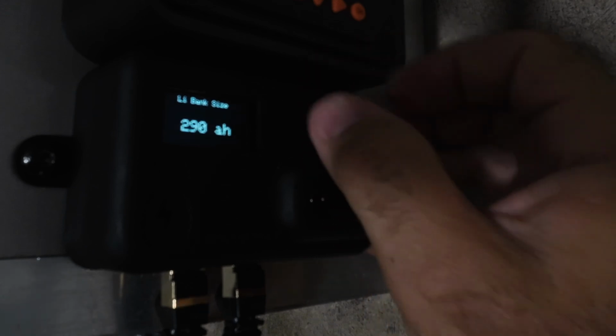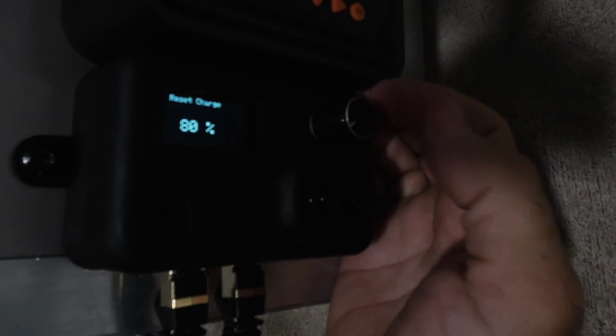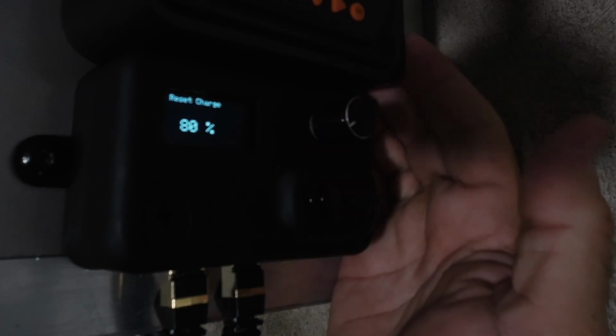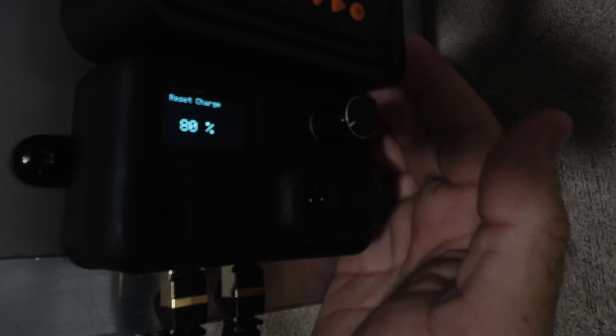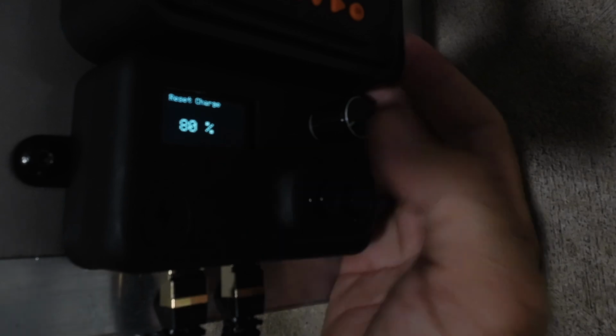And the thing that everybody has to set is how big is your lithium bank, and we're going to say 300 amp hours because that's ours. The other one, the reset charge, this says these batteries will not be a candidate for a recharge cycle until they drop below 80% of charge.